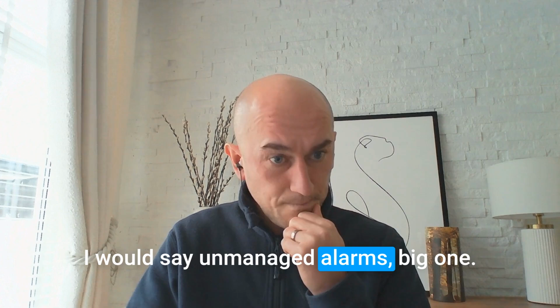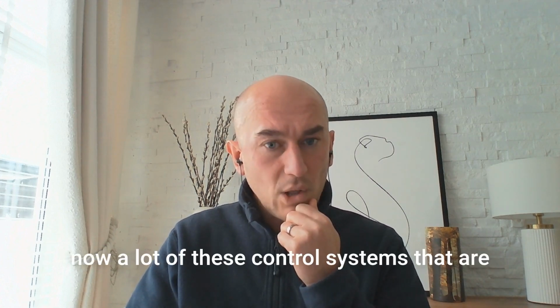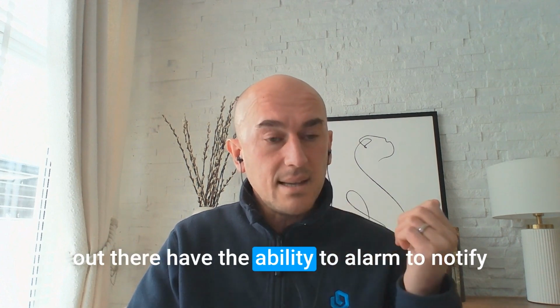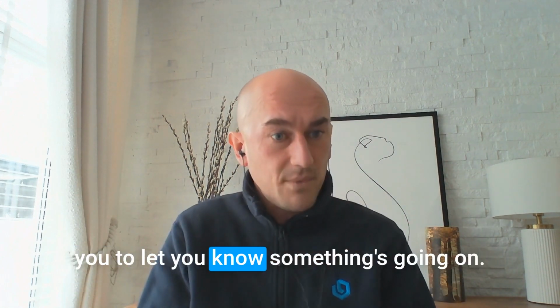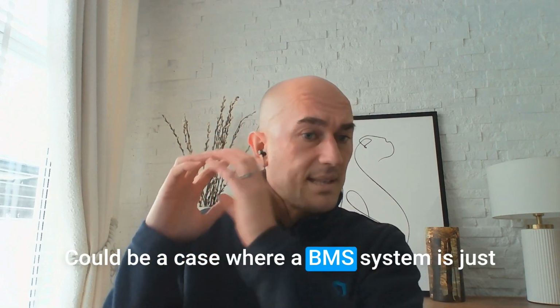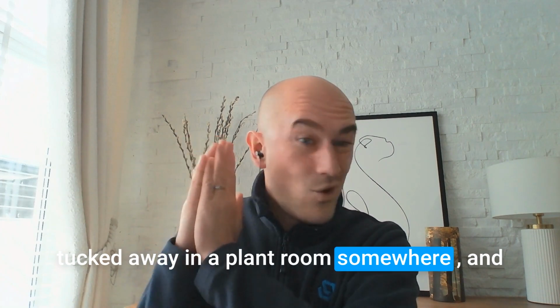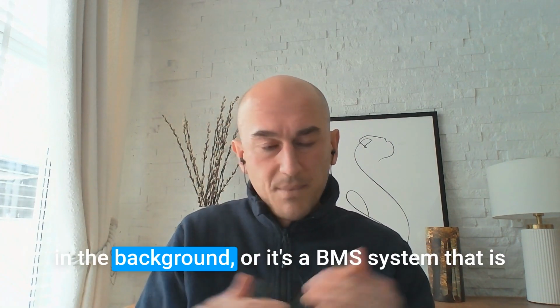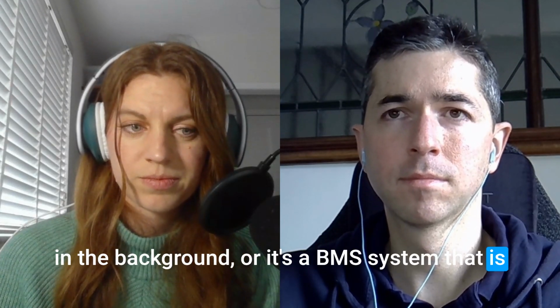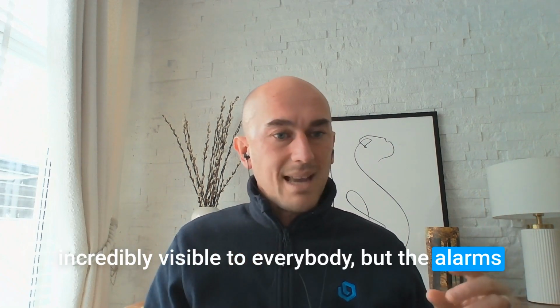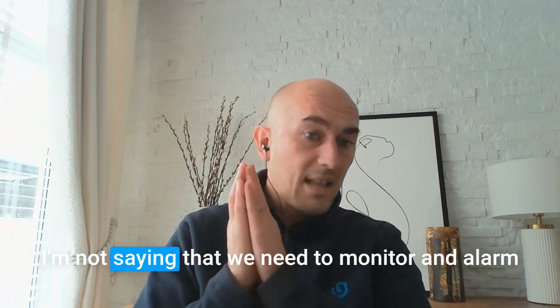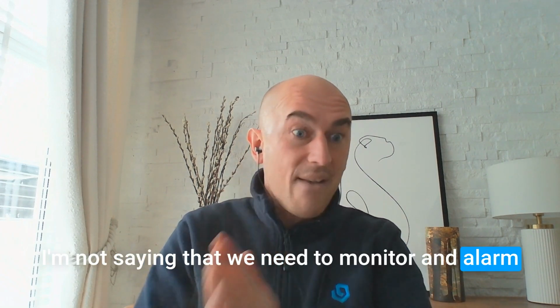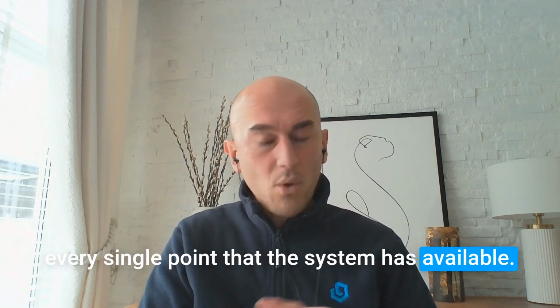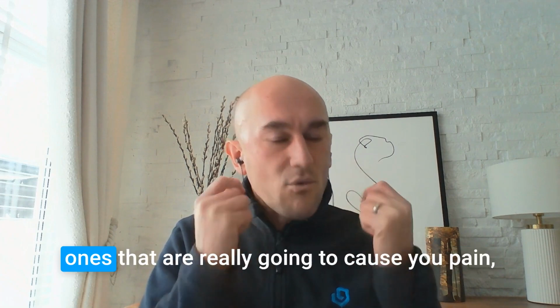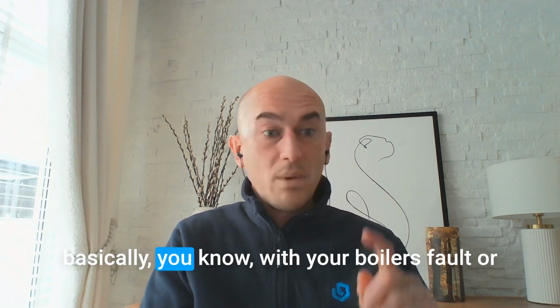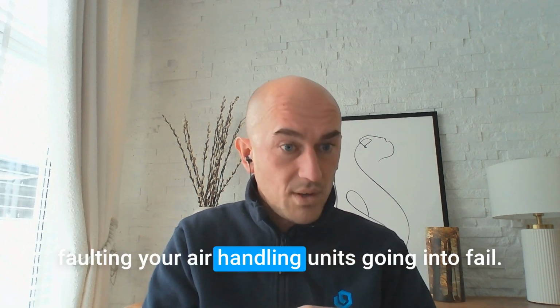Unmanaged alarms are another big one. A lot of these control systems have the ability to alarm, to notify you something's going on. It could be a BMS system tucked away in a plant room with alarms building up in the background, or a BMS that's very visible but whose alarms haven't been filtered or managed. I'm not saying monitor every single point the system has available, but take your key ones, your criticals, the ones that really cause you pain, like boilers faulting or air handling units going into fail.